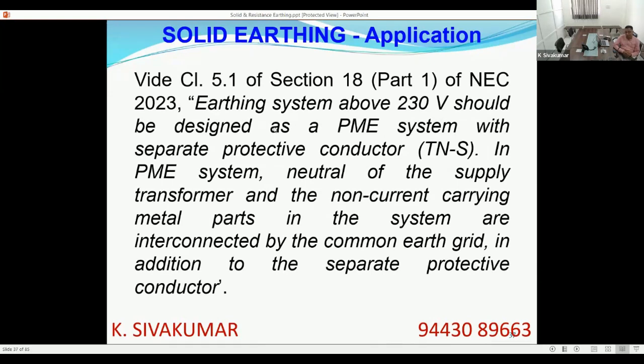If you recall, the first letter is the method of system earthing. T means terra, and terra means natural earth in French. So, IS 3043 also says that any system above 230 volt must be solidly earthed. The first letter of the network classification refers to how your system is earthed. The system neutral is earthed. T means terra. That means the neutral should be connected to terra. Terra means as close to earth potential as possible.